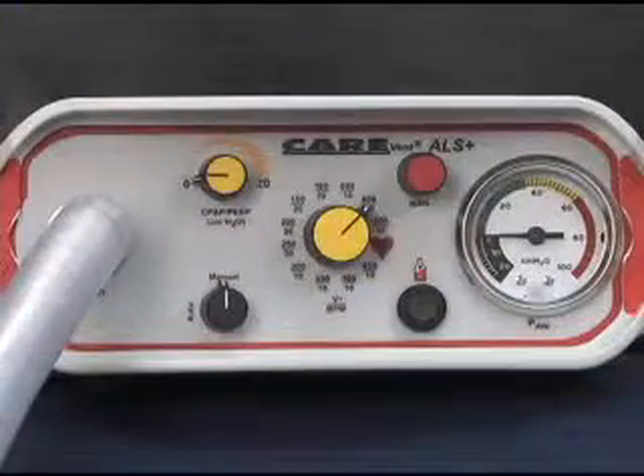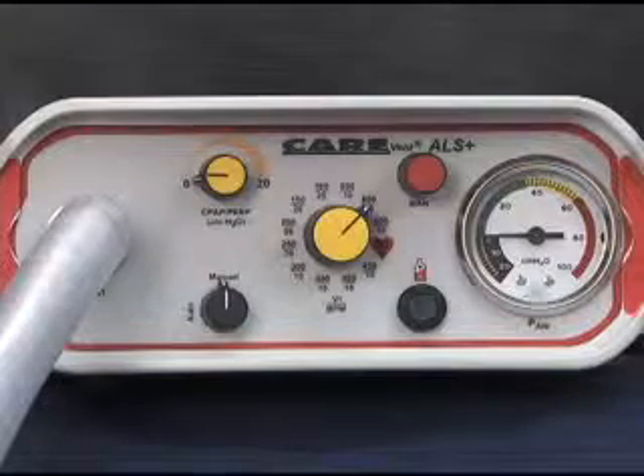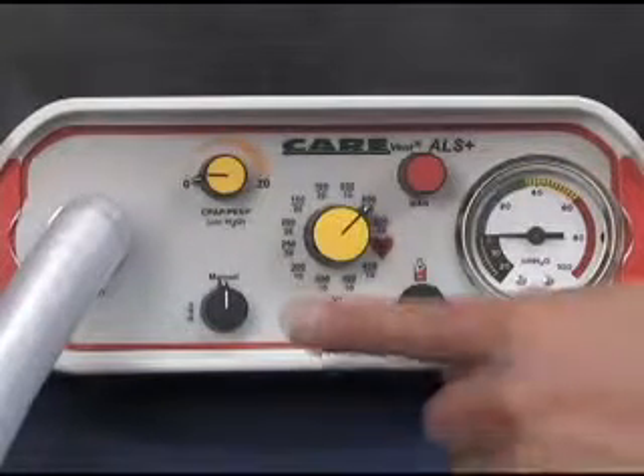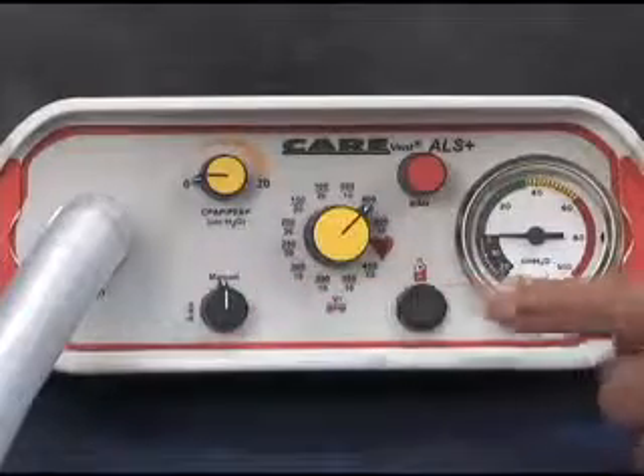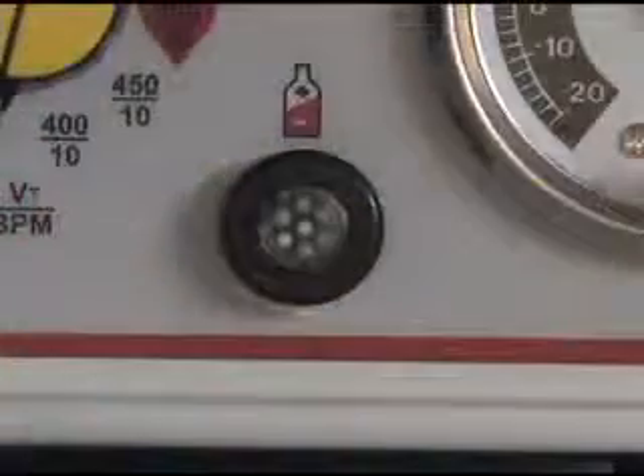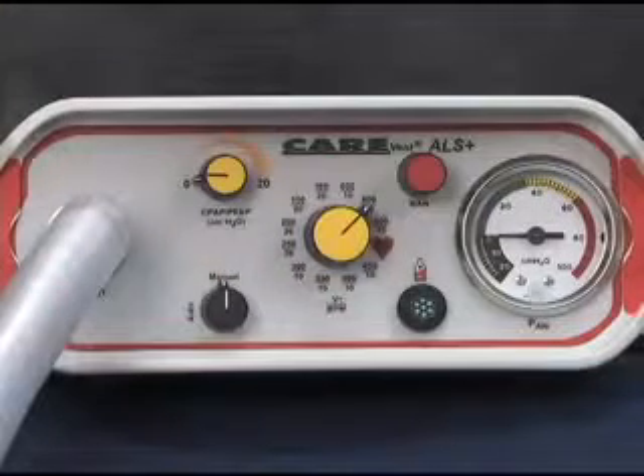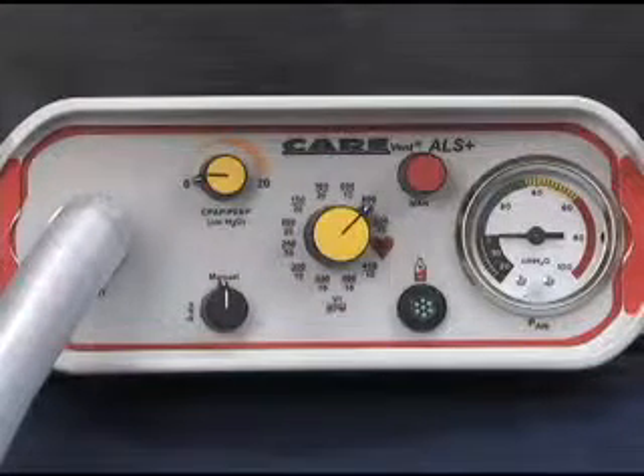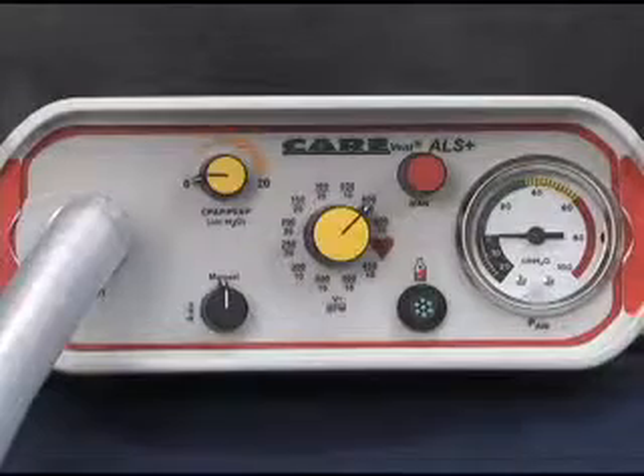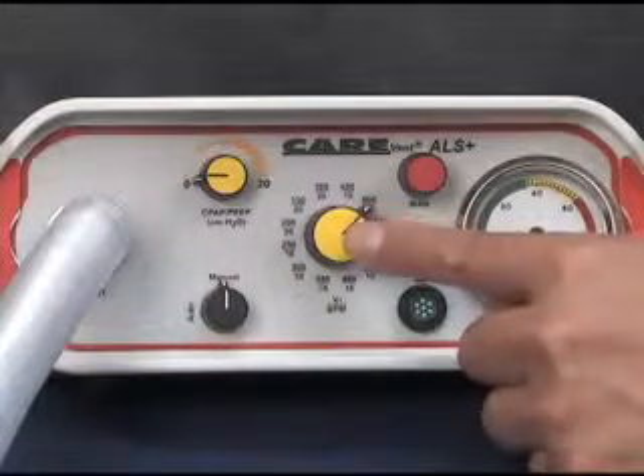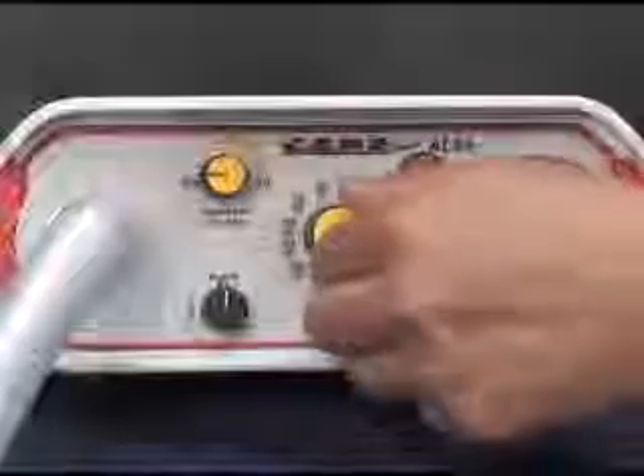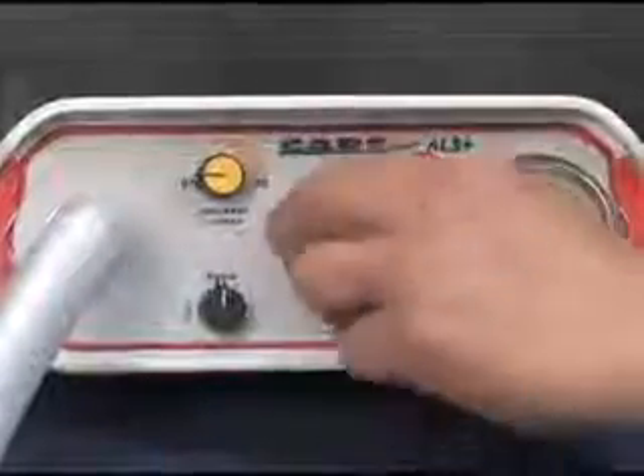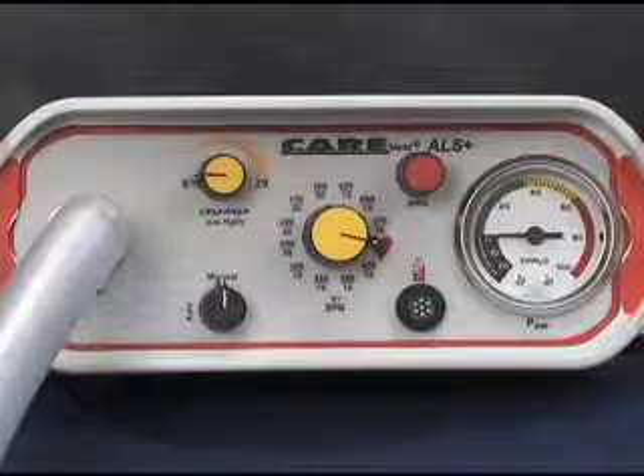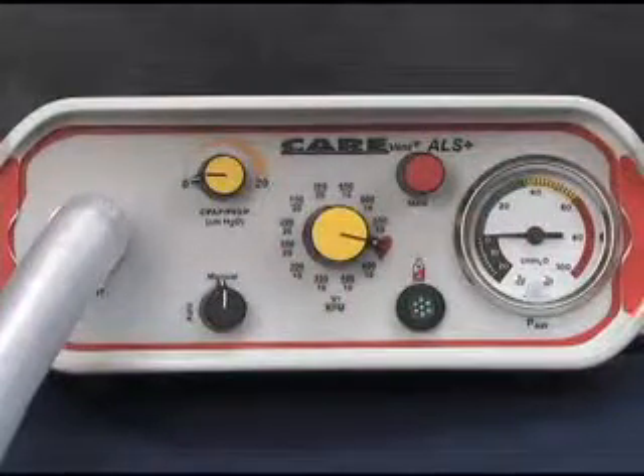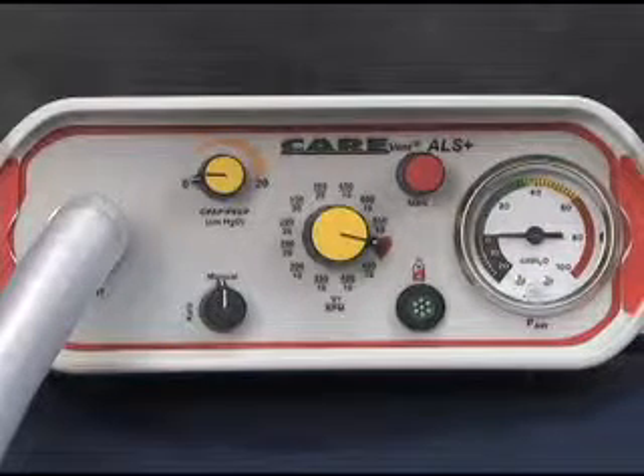The CAREvent ALS Plus and ALS Plus CPAP ventilators are equipped with three controls. The manual auto control, when in the manual position, allows the gas supply to be turned on, placing the resuscitator in a ready state for any breathing emergency. The single rotary setting selector control for the simultaneous adjustment of frequency and tidal volume provides 12 settings of automatic ventilation, with each position being preset. The range extends from small children to large adults, and all settings are calibrated in line with the current resuscitation guidelines.